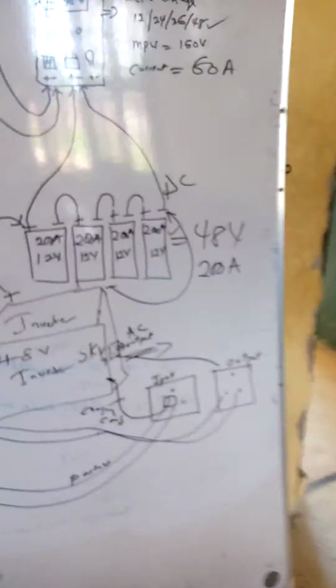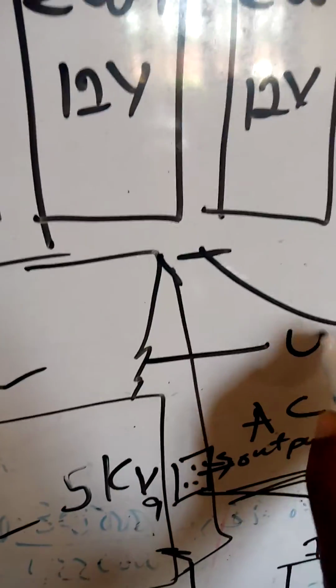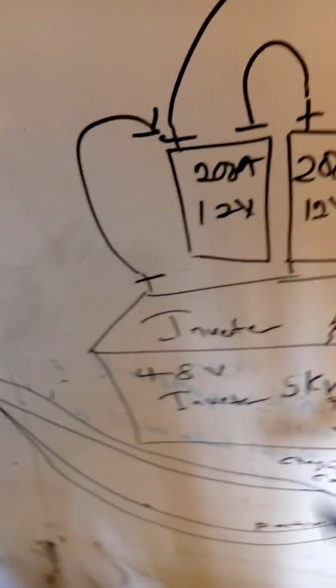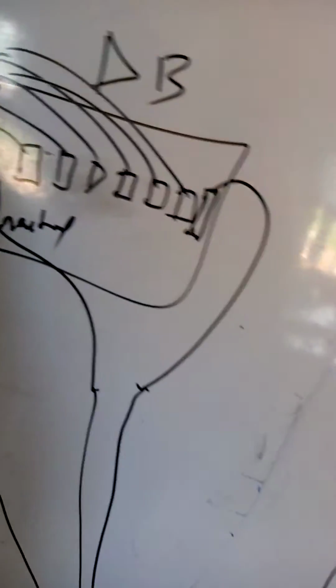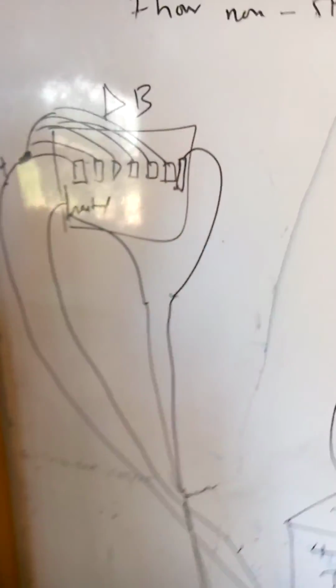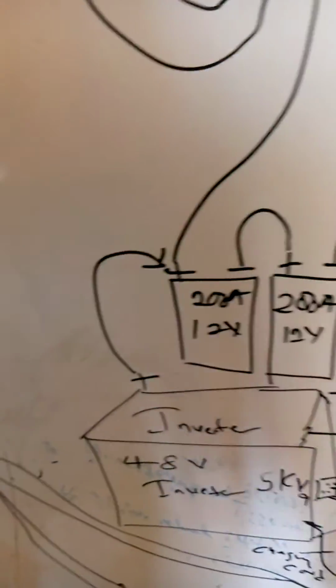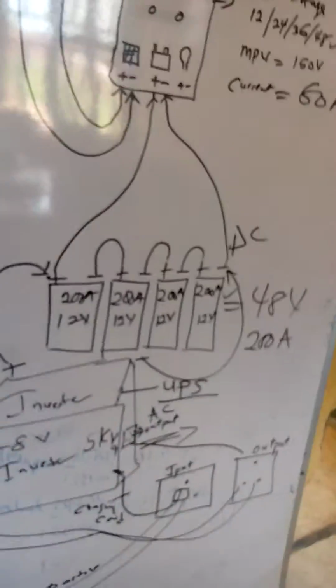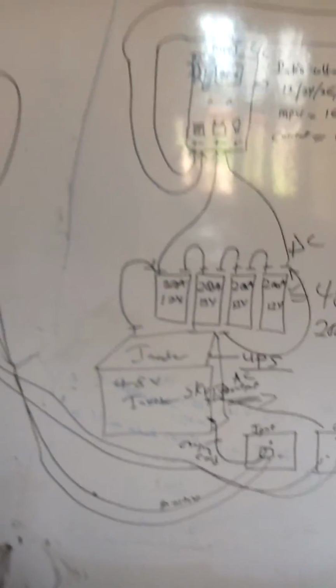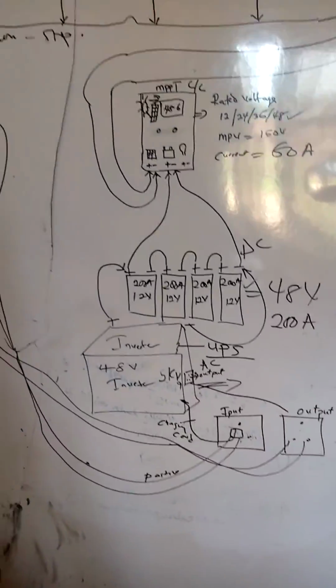The inverter stands as an automatic changeover, an uninterrupted power supply (UPS). Most inverters come with UPS function, so the inverter stands as a changeover. When NEPA is off, the system automatically changes to inverter and starts supplying current to the necessary points. When NEPA returns, the inverter automatically switches off and changes to NEPA, still serving those particular points. So the inverter stands as a changeover in the whole system.